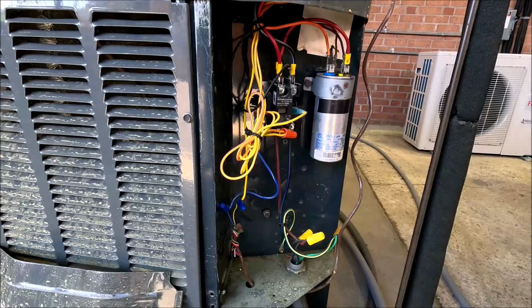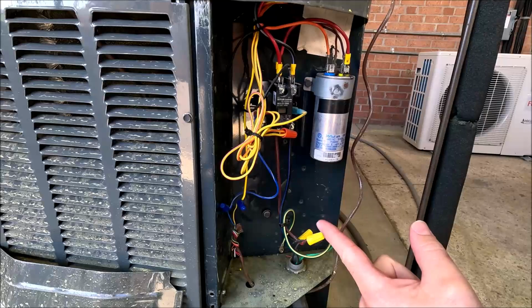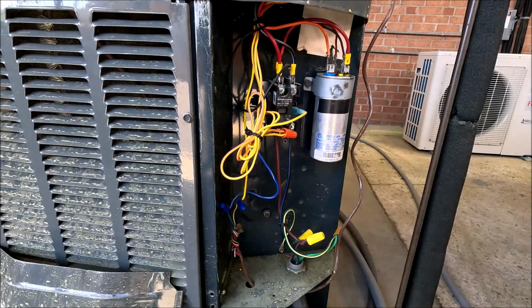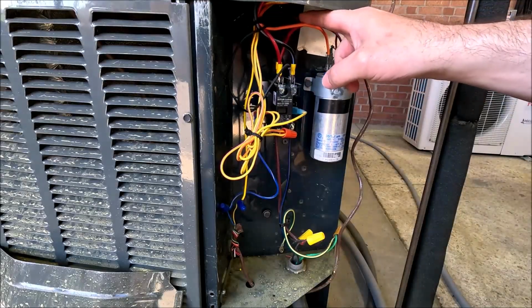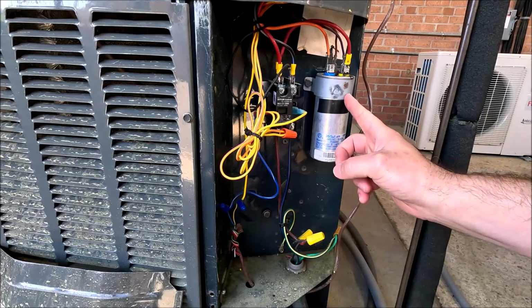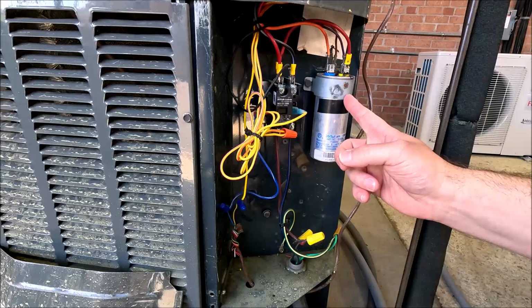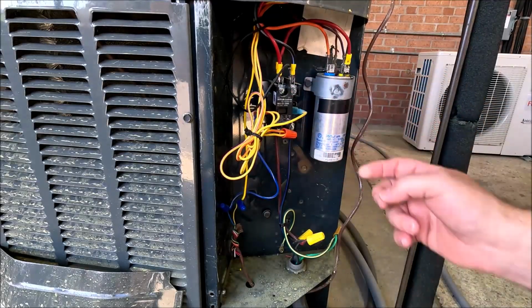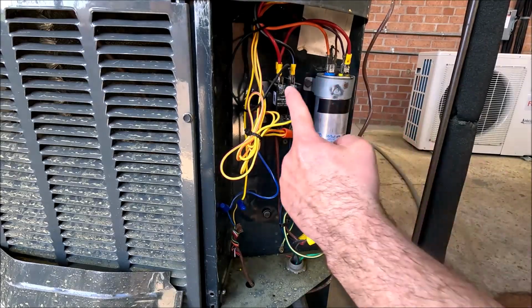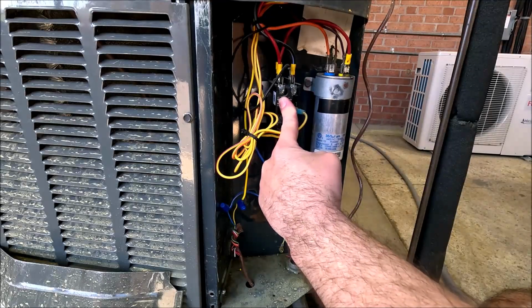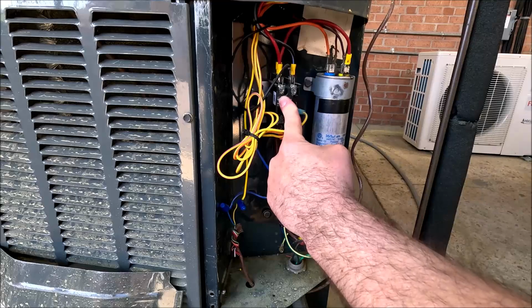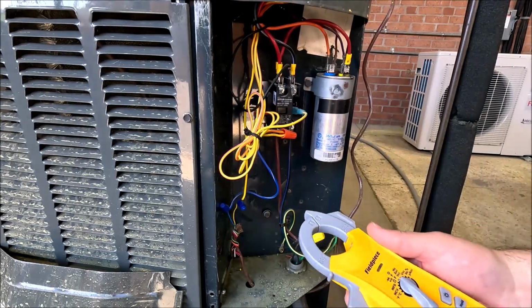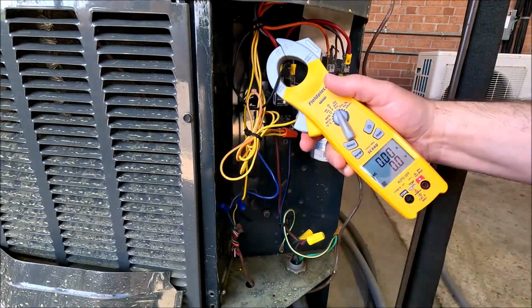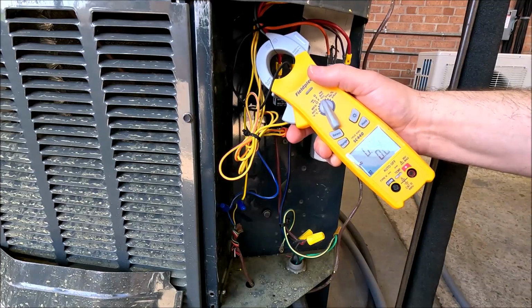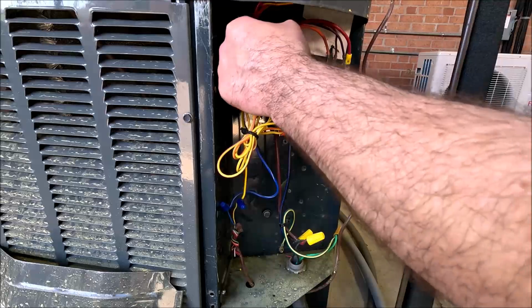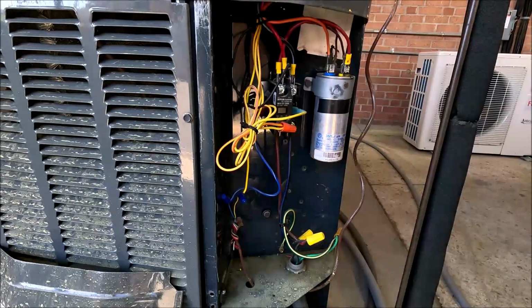But when you come off the top side of the contactor, you start getting into a little bit more. And what I look for is the capacitor. So when I look at this capacitor, I see that right here is this red wire jumping across from the left side of my contactor to the capacitor. And I know that capacitors always go on the start winding. So this L1 jumps over here so we can juice up this capacitor and hit that start winding. But this is my L1. I know the run winding also comes off of this. All right, so for me, that makes this side. So I've got 2 PSC motors out here, and this is my outdoor fan, and it's pulling, yeah, 0.4, 0.5 amps. And then this black wire here is going to be my compressor. Oh, there we go.